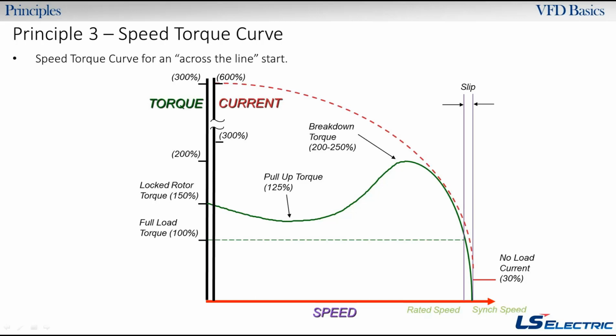But when you first close that contactor, this is your current line right here. So as far as amperage, you're going to see 6 to 10 times inrush current being pulled from that motor. So the power company loves when you do that, because if you're starting up a 200 horsepower motor across the line, they're going to ding you and charge you just for that large amount of demand that you're putting on the power company and their transformer. So if you put a VFD on there, you'll see how we could change that on the next slide.